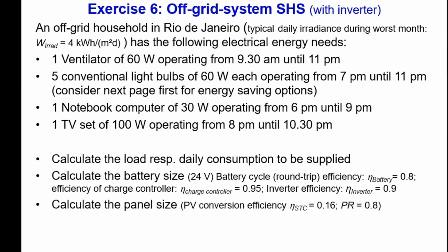We then calculate the panel size. We have a conversion efficiency under standard test conditions at 25°C. In the tropics, module temperatures are quite elevated, so we have a relatively low performance ratio of only 0.8. For the panel size, we also consider irradiance. Since the system must work all year, we take the typical irradiance during the worst month of the year. For Rio, that is 4 kilowatt-hours per square meter per day.